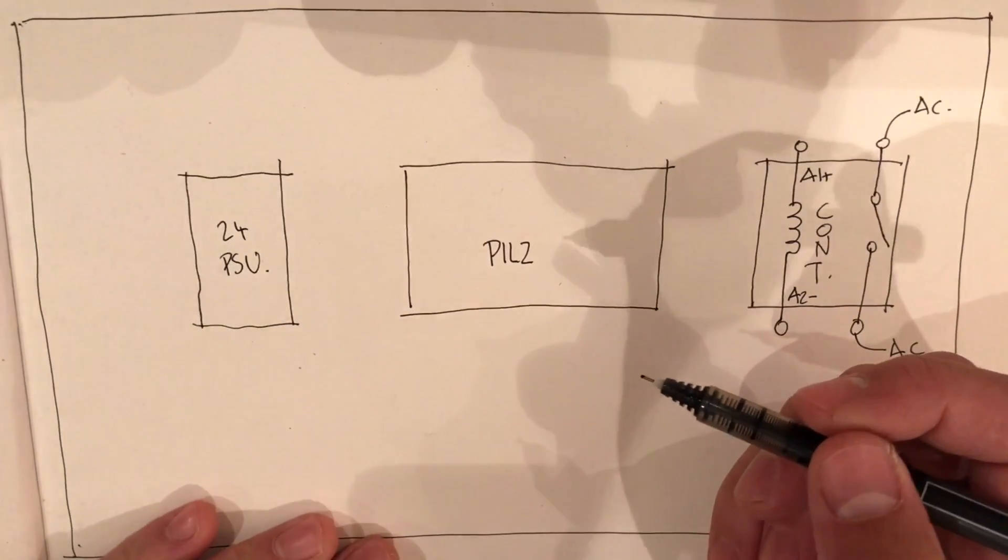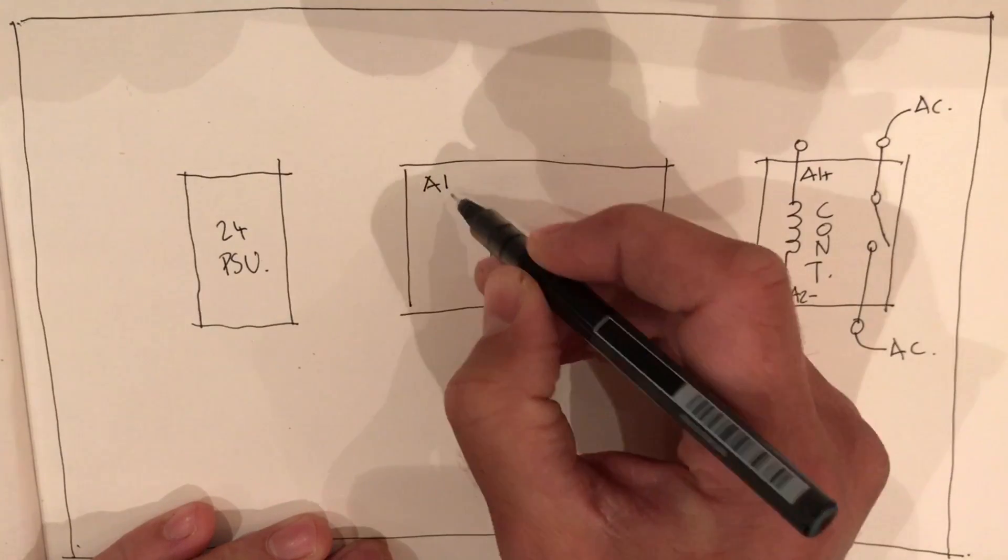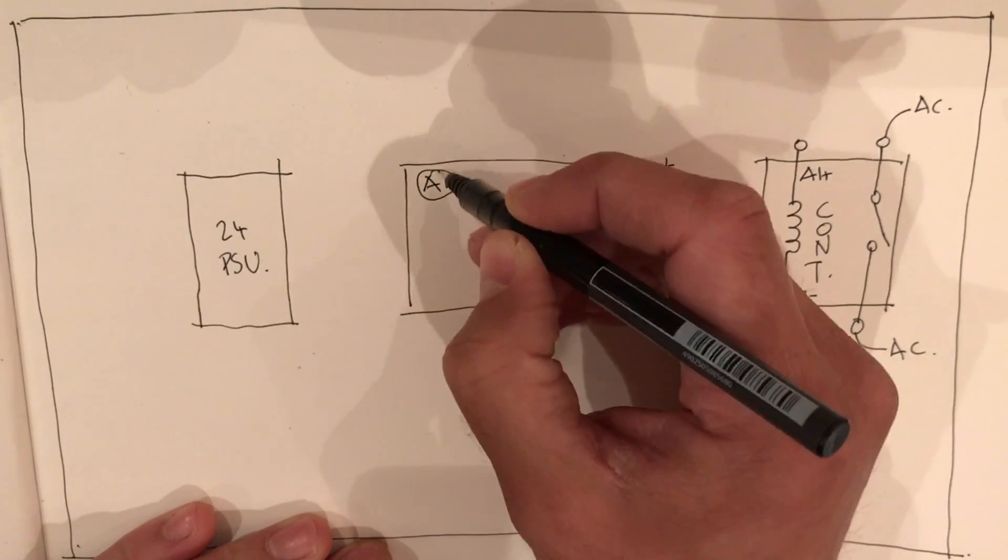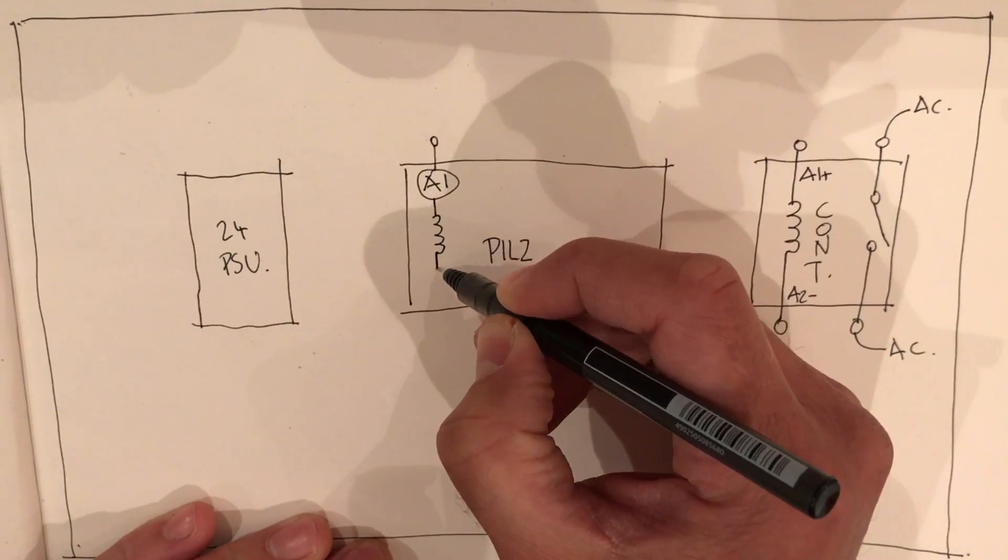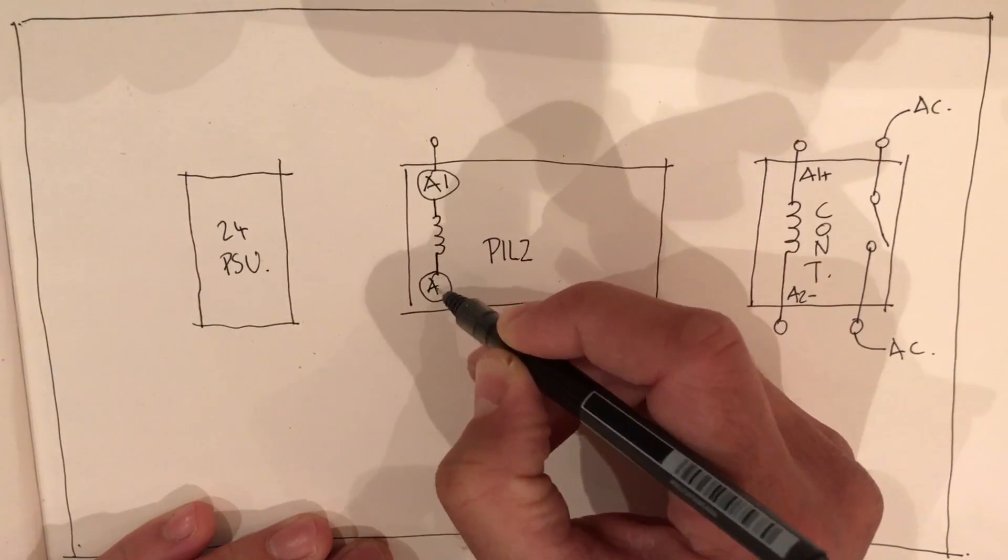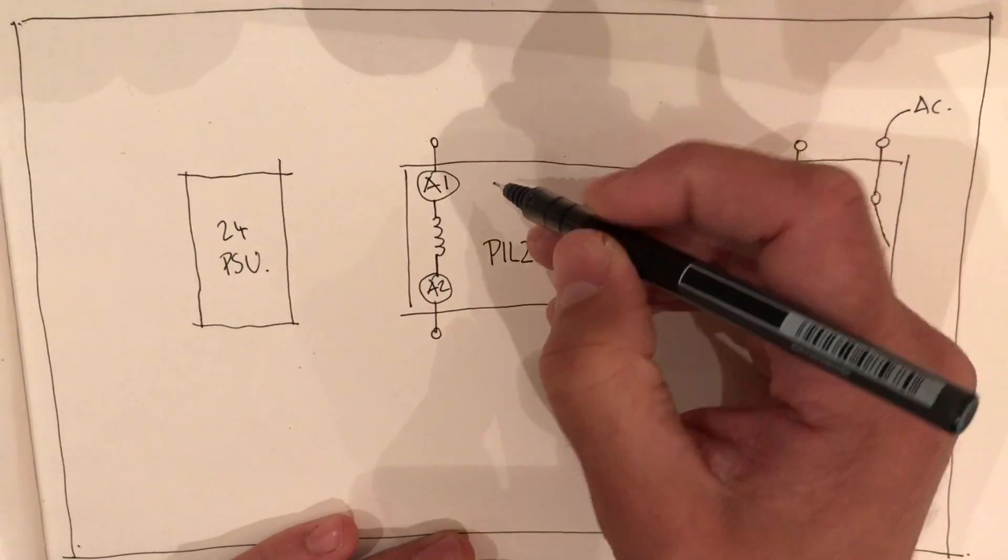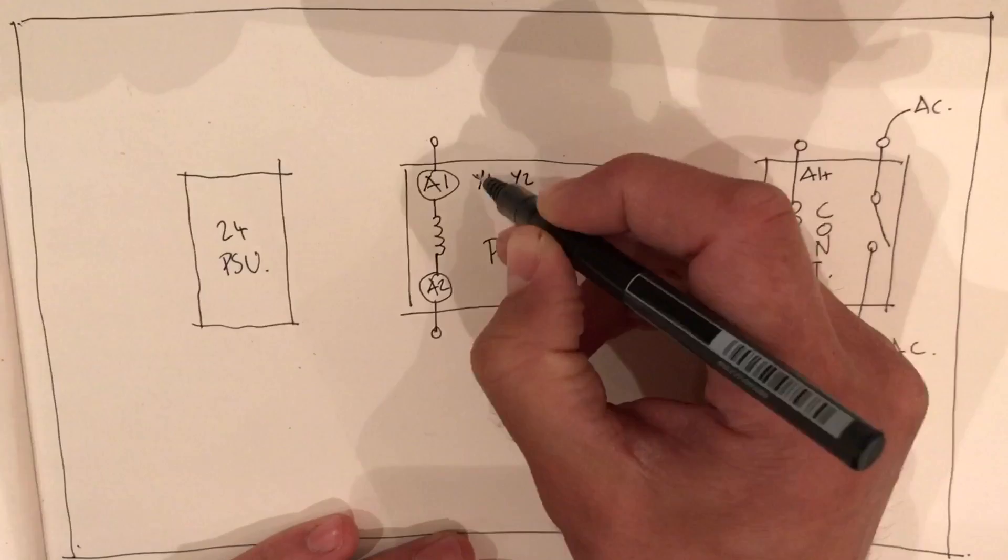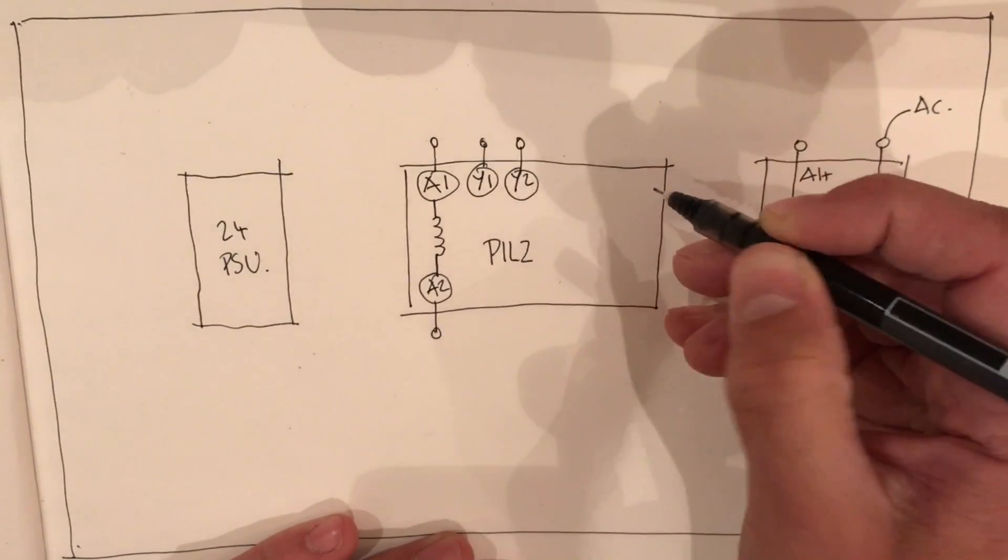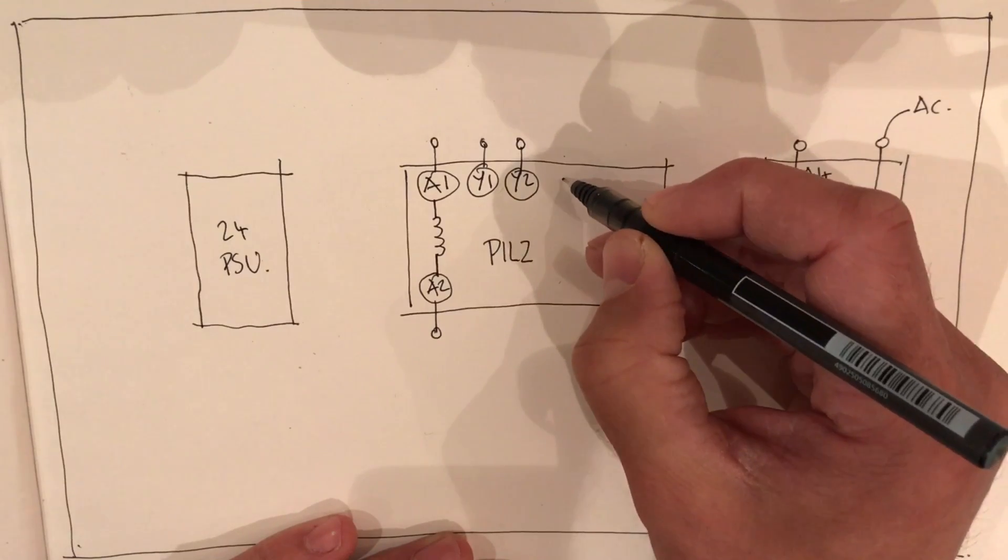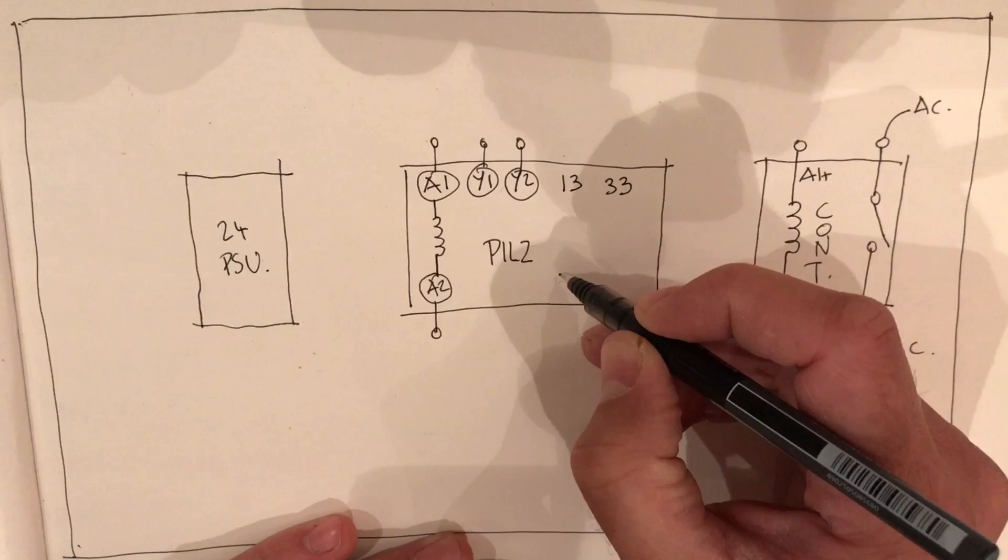For the Pilz, we've got the main coil between A1 and A2, the reset which is Y1 and Y2, and then we're going to use 13 and 33 of the switches.